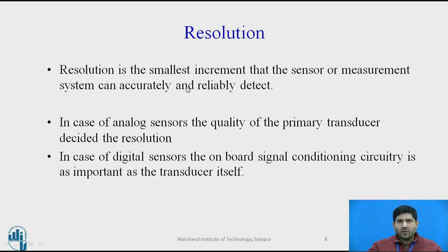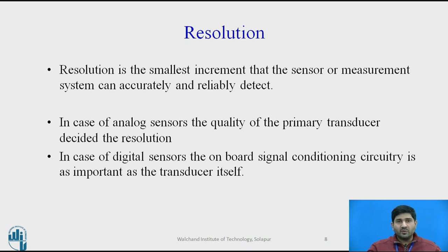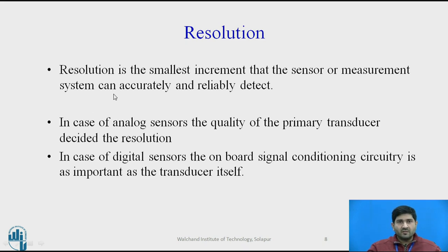Another important property is resolution — the smallest increment that the sensor or measurement system can accurately and reliably detect. In the case of analog sensors, the quality of the primary transducer often decides the resolution. In the case of digital sensors, the on-board signal conditioning circuitry is as important as the transducer, most critically the analog-to-digital converter. Poor resolution of the ADC limits performance no matter how good the original analog primary transducer is.